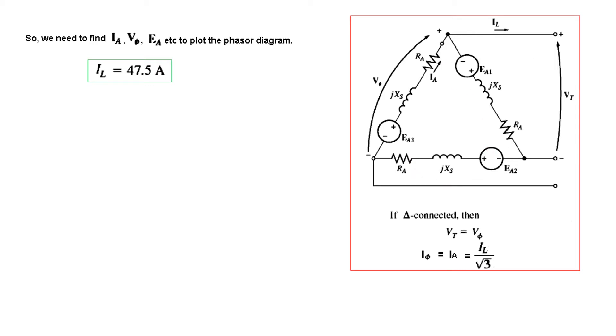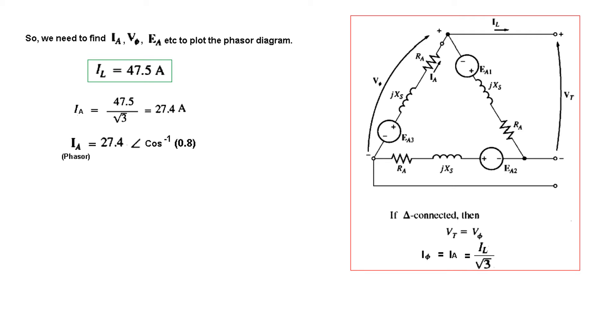In a delta connection, the terminal voltage equals the per-phase voltage, so Vt = V_phase. However, the line current is greater than the phase current. The armature current Ia equals the line current divided by √3, so Ia = 47.5 / √3 = 27.4 amperes. For the phasor plot we also need the phase angle: Ia phasor = 27.4 at angle cos⁻¹(0.8) = +36.87 degrees.